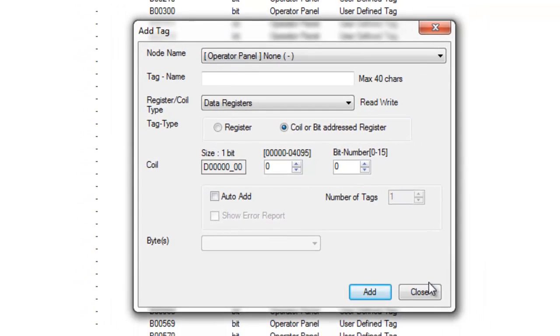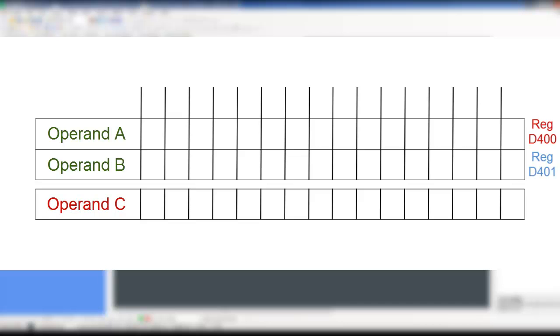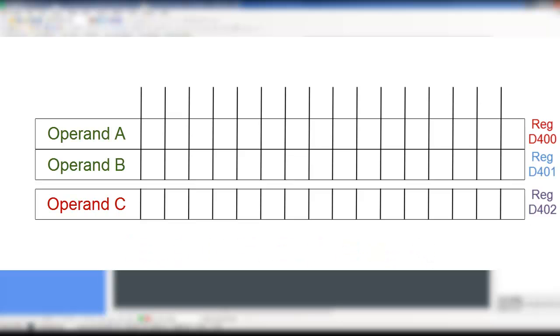The AND logical operator allows us to choose 3 registers for 3 different operands. Operand A and Operand B are both input registers. Operand C is the output register. If both Operand A and Operand B are turned on, the AND logical instruction turns on Operand C. Otherwise Operand C is turned off.